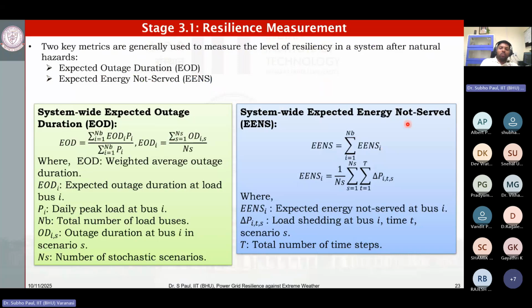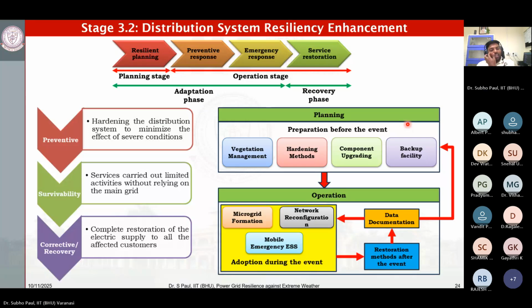And to minimize this effect, we take certain measures, or you can take certain steps for this distribution system resiliency enhancement. And there comes the planning stage. We can do it at the planning stage and we are doing it at the operation stage. What is actually your short-term resiliency and your long-term resiliency? So the long-term resiliency actually includes your planning, where you will do the vegetation management. That means you will take care that a branch of a tree will not fall down on your power lines. You will do the hardening methods. That means what I told, that you will use, let's say, concrete or steel poles by replacing your wooden poles, and you will use bundle conductors rather than single stranded conductors.